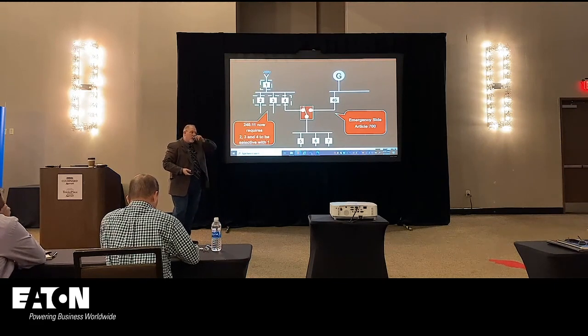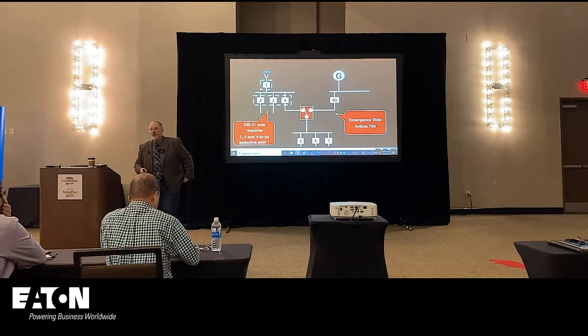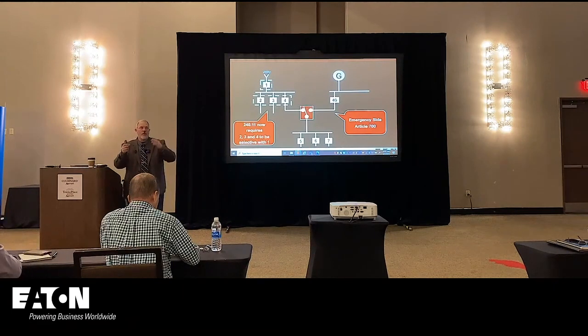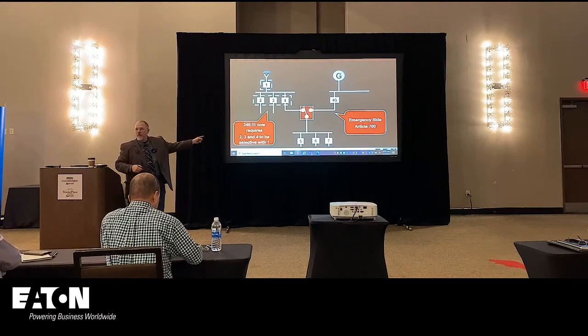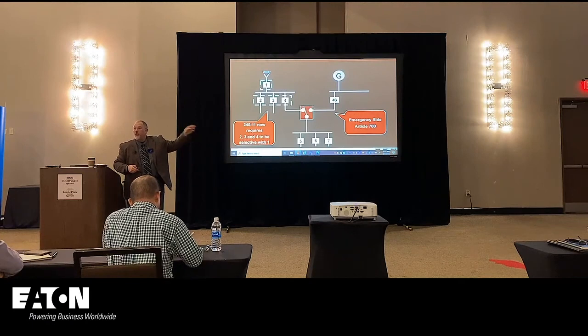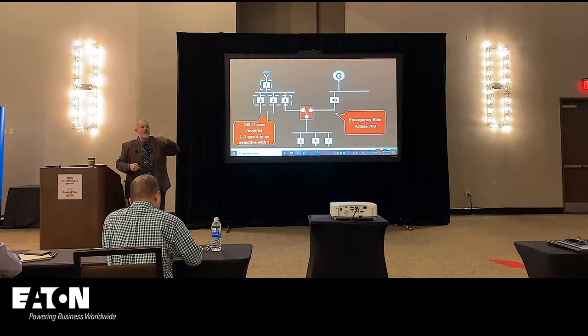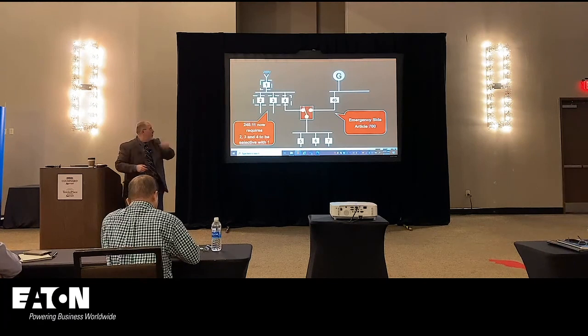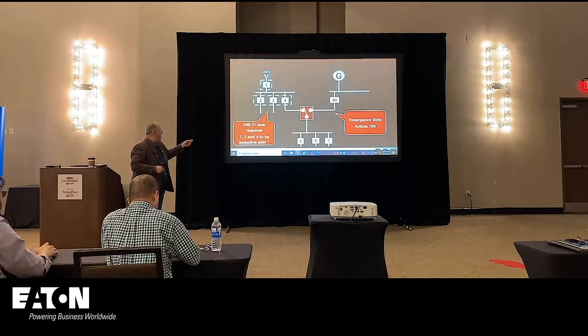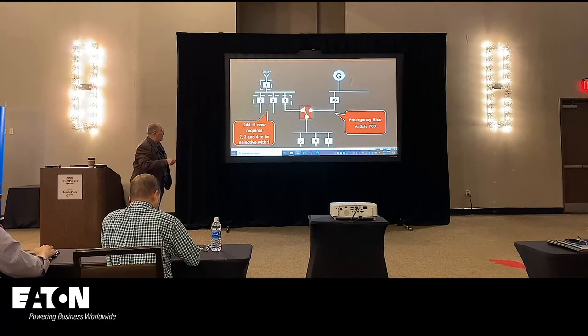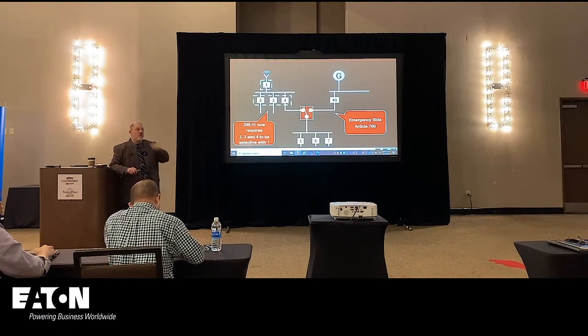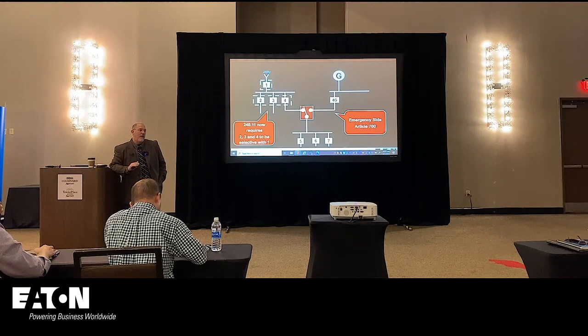So panel 10 said, you know, we're worried about the reliability, and from a failure mode, from a reliability perspective, transfer switches may not transfer. Generators may not start. So if I can avoid the transfer, then I've increased the reliability of the system. So in 240.11, we now require, when you are feeding a system where the overcurrent devices downstream of that transfer switch have to selectively coordinate with the normal side, which is your Article 700, 701, 708, I've got a list of them, then you have to selectively coordinate the main with the first level overcurrent devices. So the main and the immediately connected branch or feeder breakers.